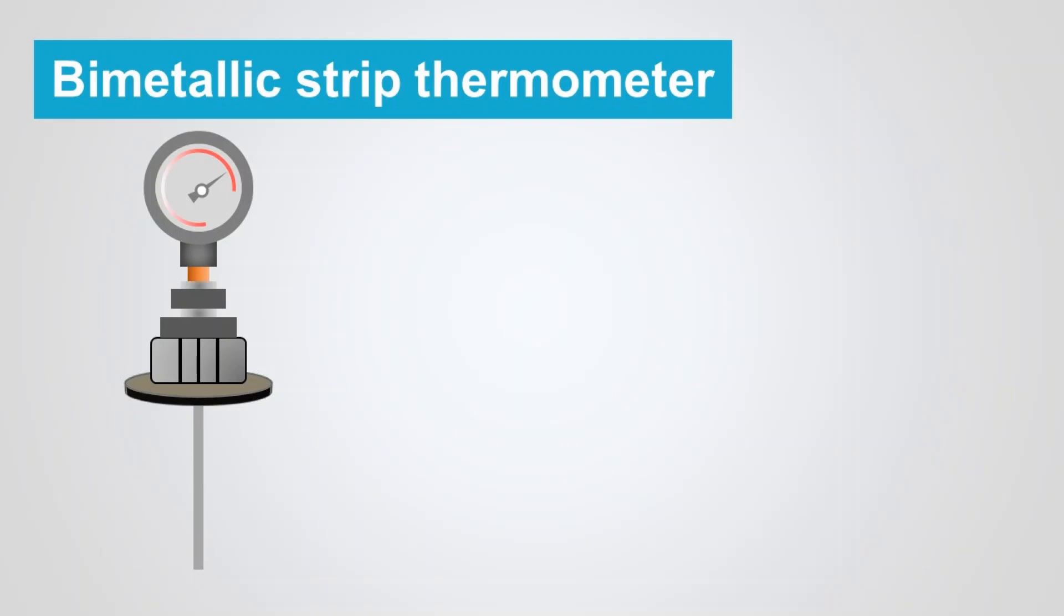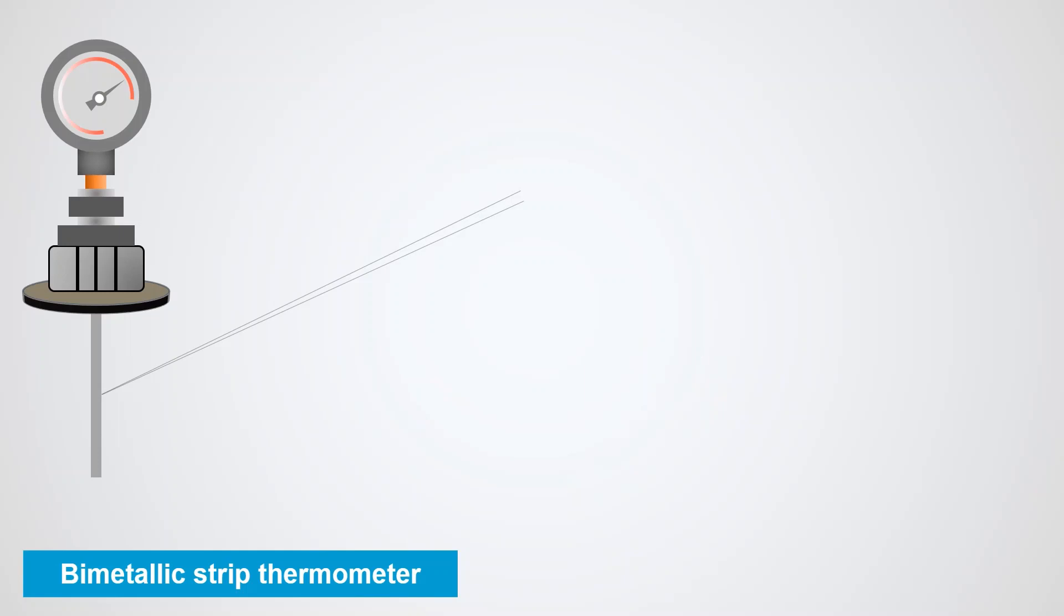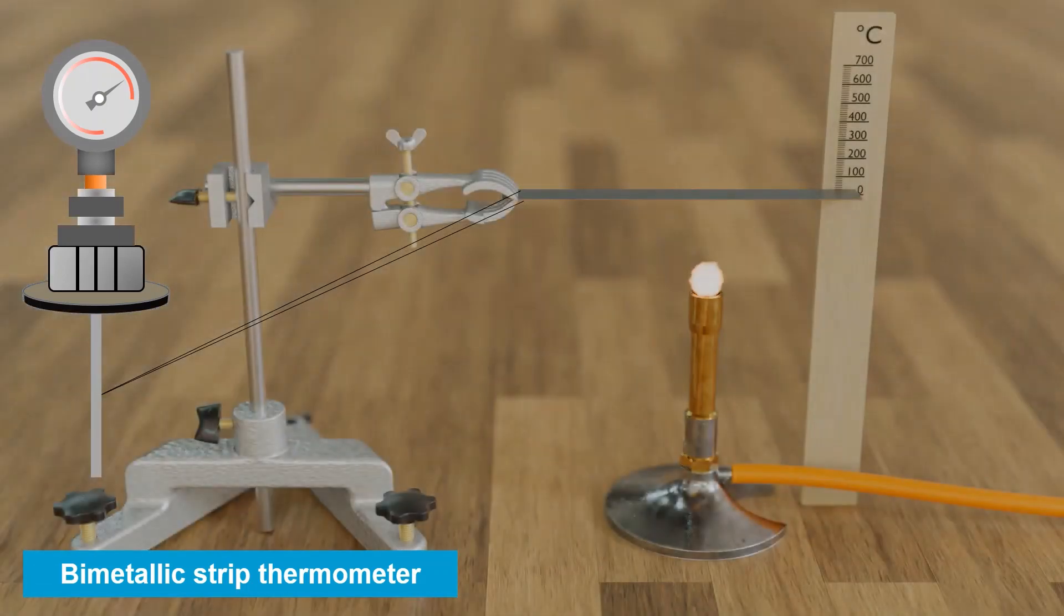A bimetallic strip is a very widely used method of temperature measurement. This method is based on the principle of thermal expansion of solids when there is a change in temperature. Bimetallic strip, as the name implies, consists of two metal strips with different degrees of thermal expansion firmly bonded together. When the strip is subjected to a temperature higher than the bonding temperature, the metal strip deforms due to the different degrees of expansion in one direction. When subjected to a temperature lower than the bonding temperature, it bends in the other direction. The deformation is a measure of the temperature and can be read off a calibrated scale.